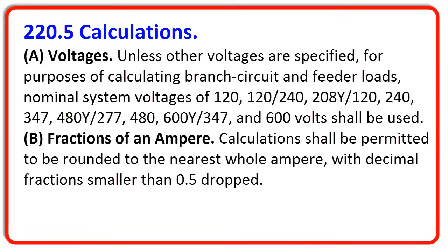We are now out of Article 210 and have moved into Article 220. Let's start in 220.5. This gives us our nominal voltages that we have to use for calculations. The word nominal means in name only. Our nominal voltage for a dwelling unit is 120/240. Now that doesn't mean that we might not have 112 volts, or maybe 220 or 228 somewhere in there. We don't really know exactly what we're going to have at each and every dwelling unit, so we have to have some sort of benchmark to base our calculations on.